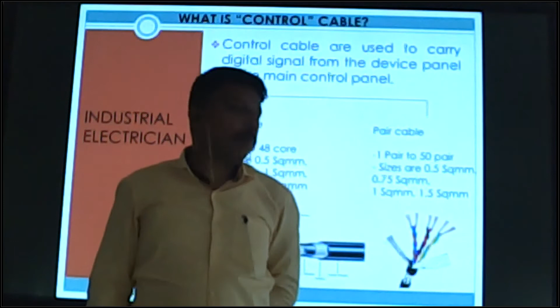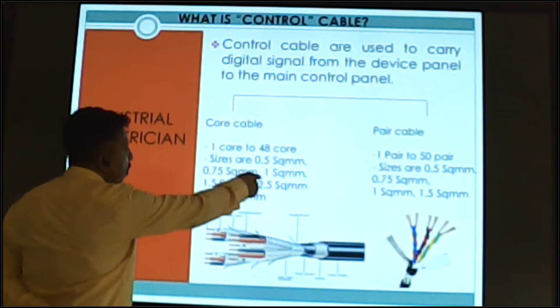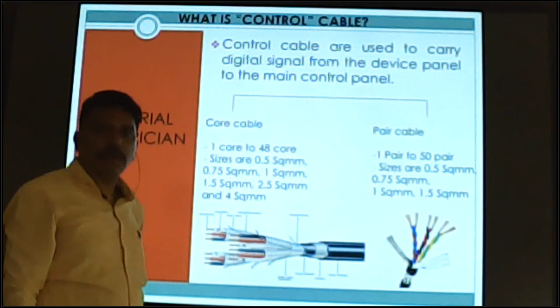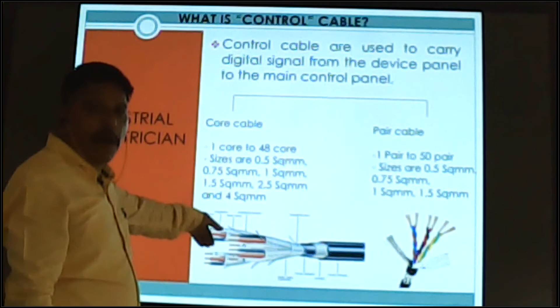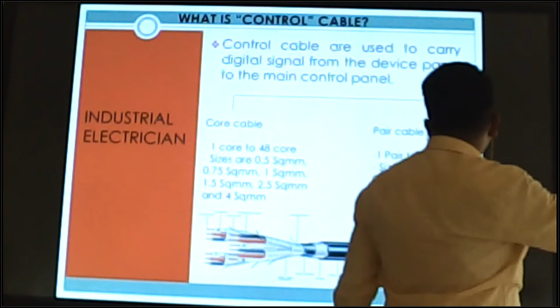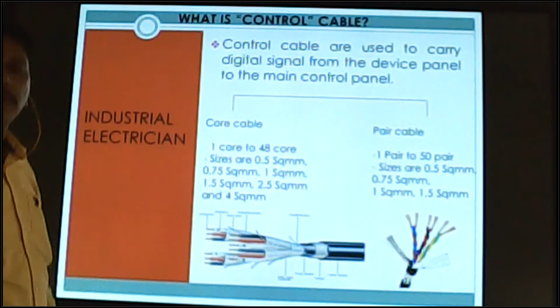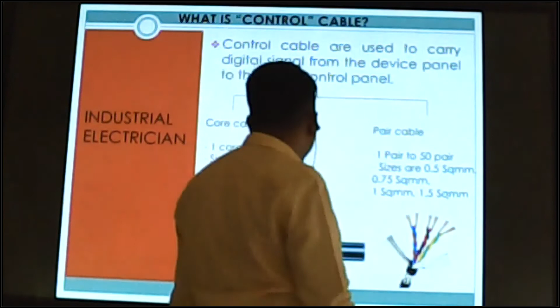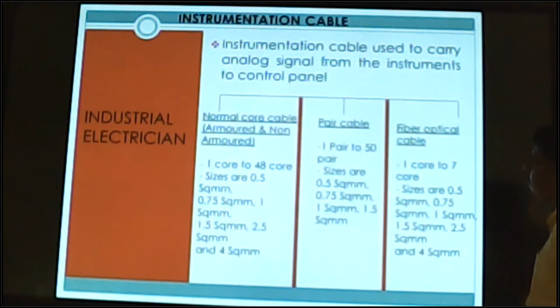The available sizes are 0.5 mm square to 4 mm square: 0.5, 0.75, 1 mm, 1.5, 2.5 and 4 mm. As per site requirement, we use these cable sizes. Pair cable comes in the same sizes, 0.5, 0.75, 1 and up to 1.5; 2.5 or 4 mm is not available in pair cable. We use them as per site requirement. Is it clear? Okay, next one.